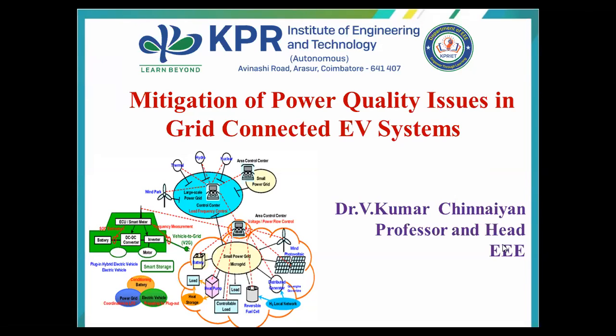When it comes to generation through inverters of any kind, we process the power, that is, the DC power, which is converted into AC. There come the issues of power quality. So while interconnecting these generating stations, we are supposed to experience power quality issues. At the consumer end also, we have power electronic systems or power processing units, which again create power quality issues. That is, again, it disturbs the voltage waveform, the current waveform, and the frequency or the shape of the waveforms.